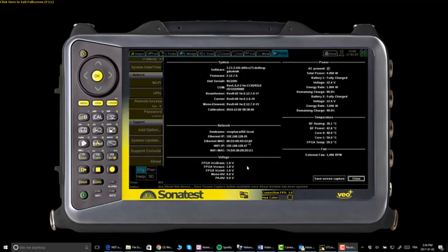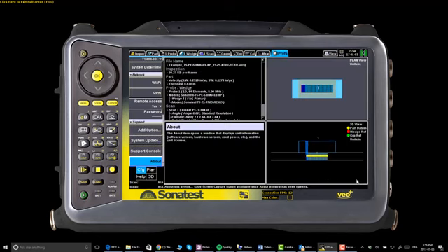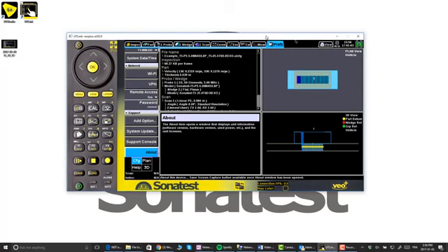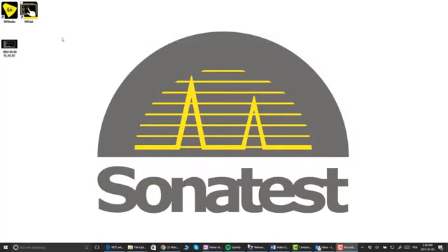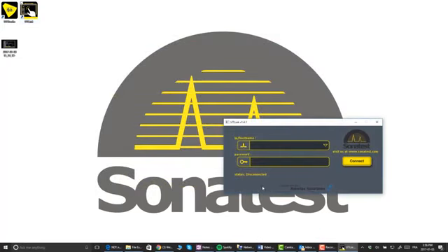I am now going to demonstrate leaving this UTLink session connected by Ethernet cable, and I'm going to create a new session using the IP address generated by the Wi-Fi connection. The new address generated ends with a 0.47 instead of a 0.45. As I didn't change my password, I just have to press on connect and I'm now controlling my VEO Plus through the Wi-Fi signal.